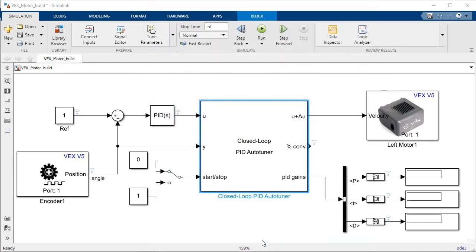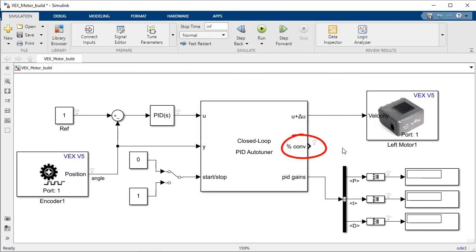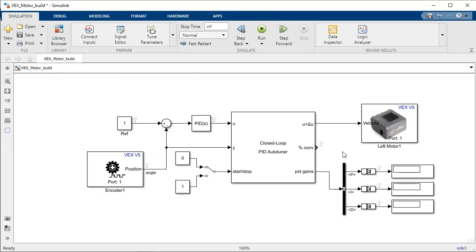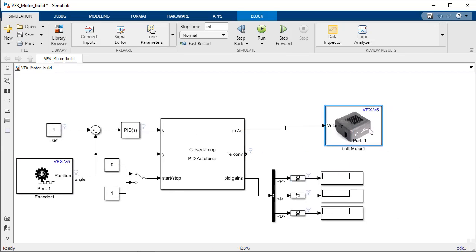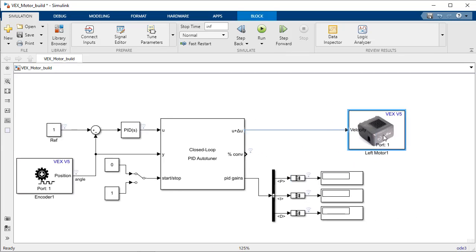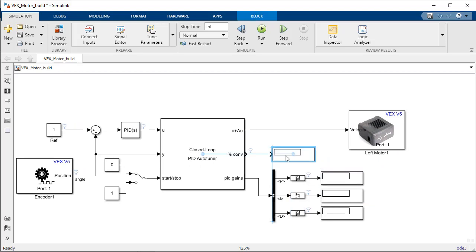To determine whether the test is successful or not, you can monitor the test convergence using the second output. Once we start the test this value should converge quickly and once it gets close to 100% you can stop the test and record the PID gains calculated.